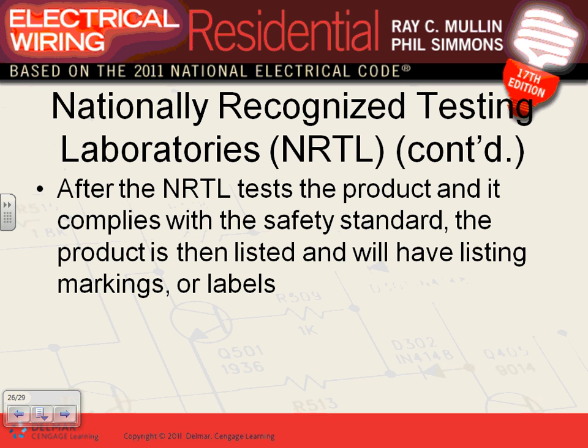What they do for third party verification is take a 4,000 amp switchgear, put it right here, pump 4,000 amps on it, and let it sit for a while to see if it's going to explode. Basically, they test things by trying to blow them up. Then they put 65,000 amps in the circuit breaker to see if it will trip, how fast it trips, and whether it explodes in the process. If it meets the specification, they give it a label, stamp it, and list it as suitable for this application.